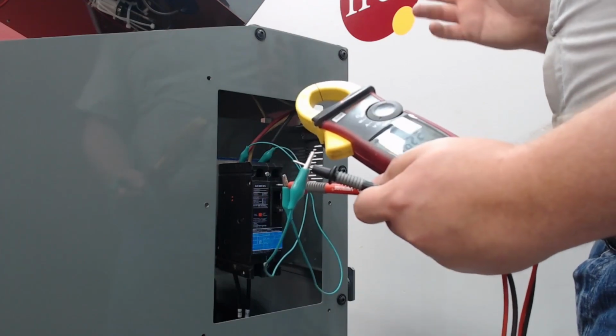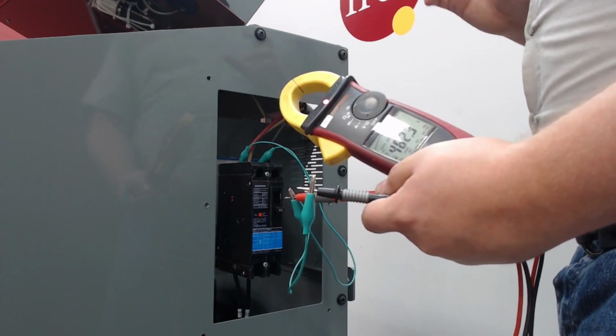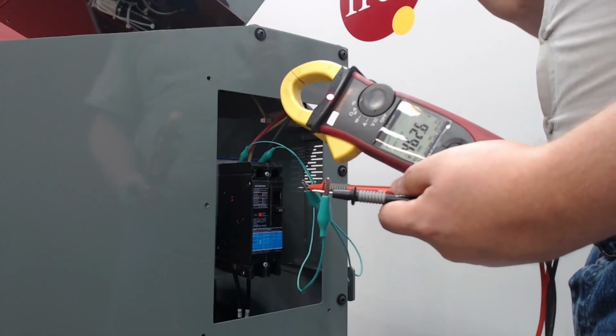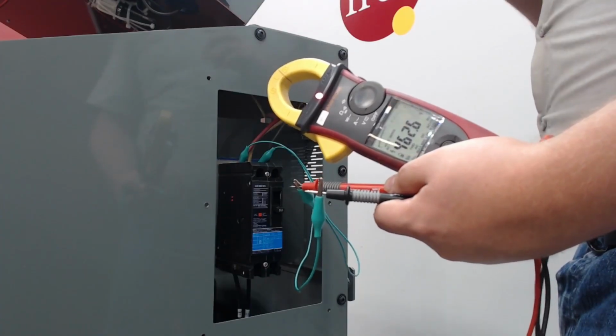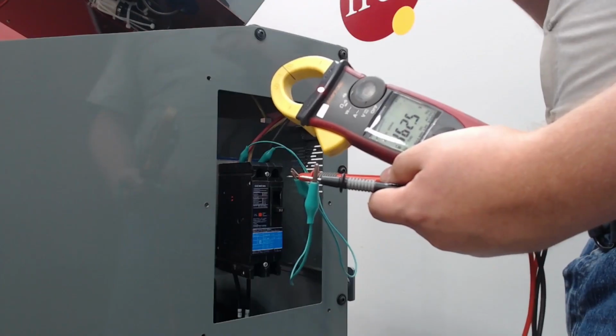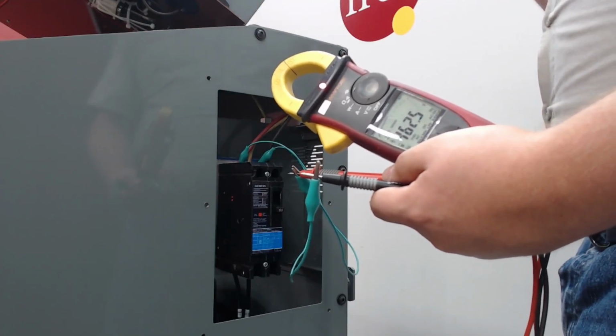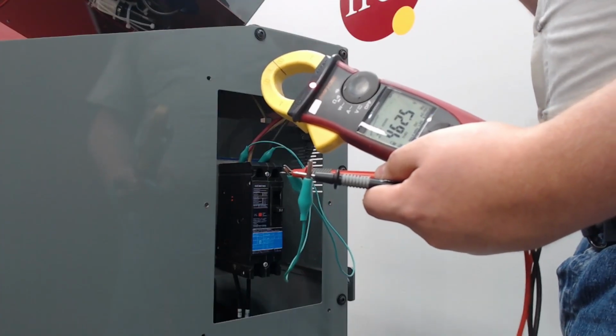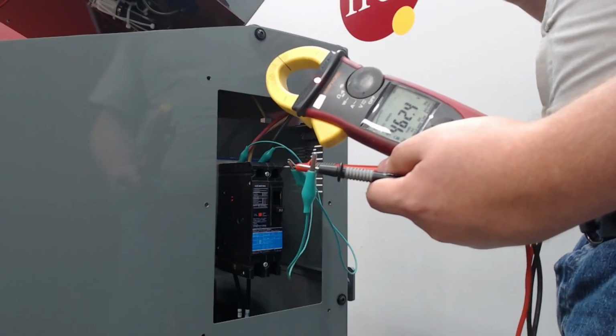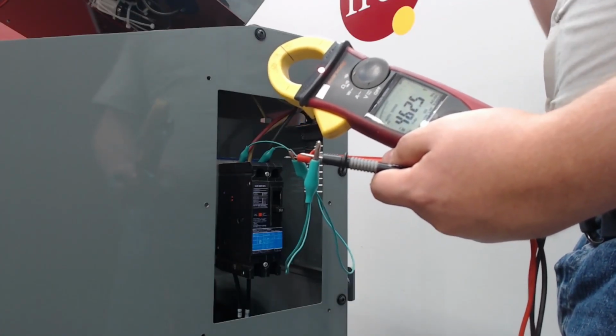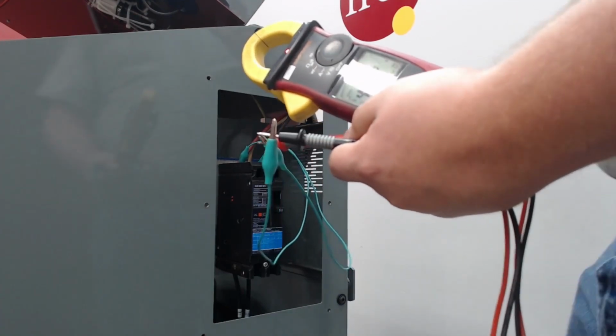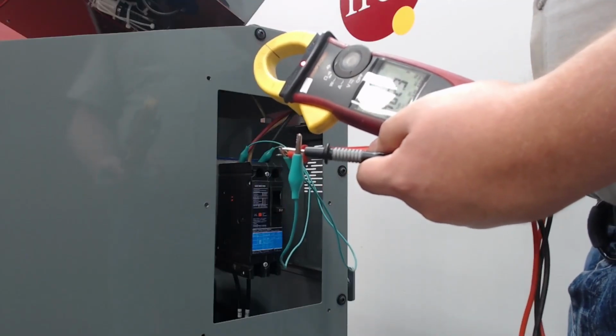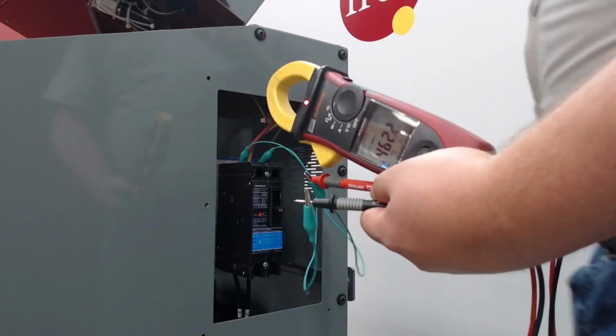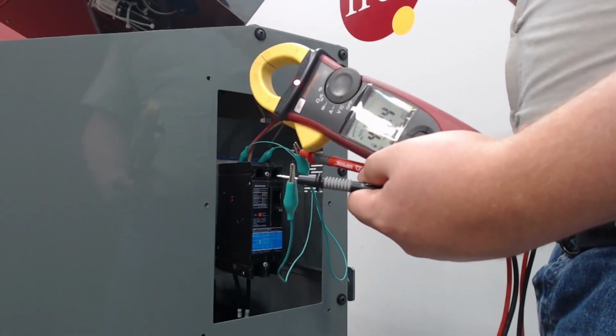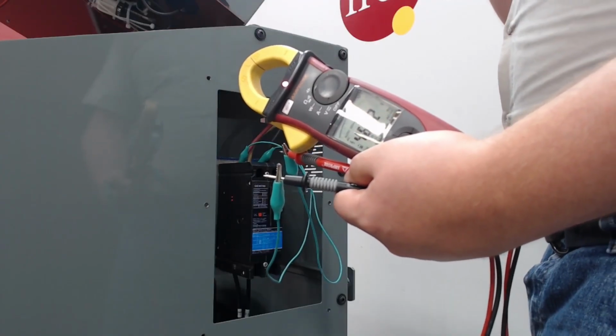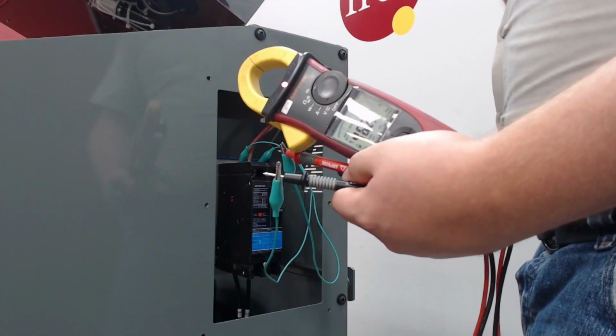So we're going to go over the main culprit, which is going to be voltage drop. Sometimes transformers can age out or components can go bad, but most of the time that we've experienced this, especially with a new customer, a new setup, a different facility, maybe a different part of the facility, it's going to be your power panel is not enough to handle the inrush current that these machines pull. So for a split second, when you turn them on, they pull the max amps and it probably even exceeds it for a split second. So that is the inrush current. You need time delay and you need your fuses and breakers to be set up to handle inrush current. Not all breakers will be designed to; they'll trip immediately the moment the amp is exceeded, and so you need the specific equipment to handle inrush.